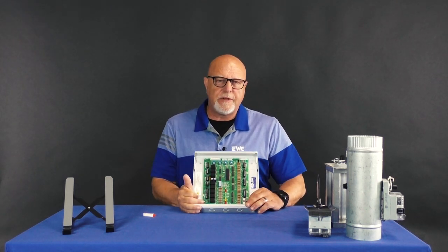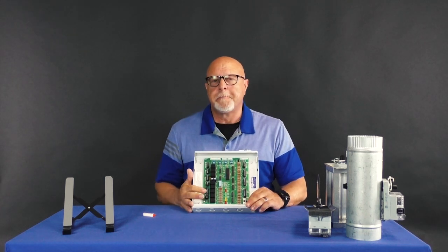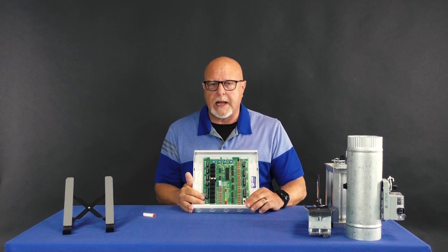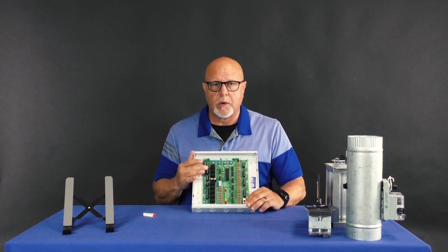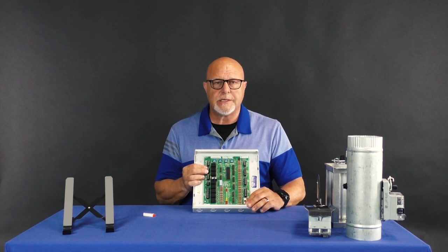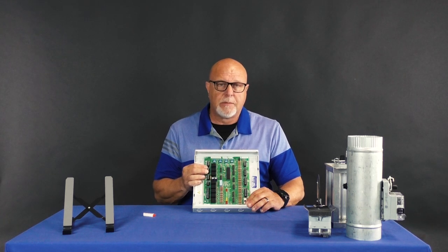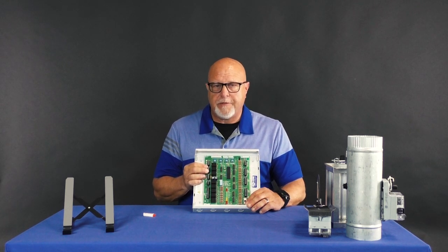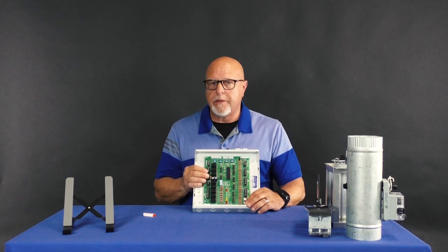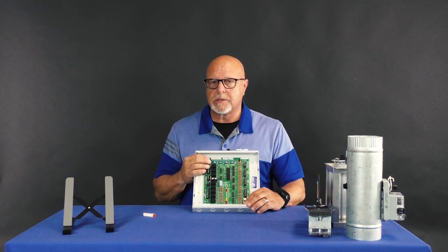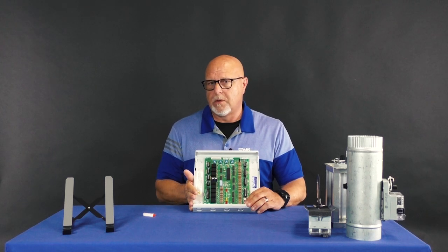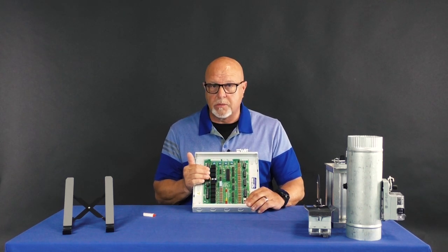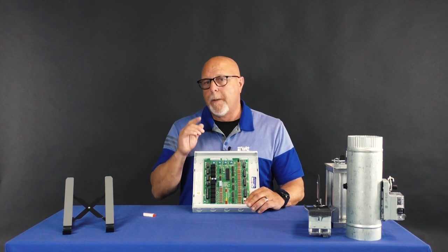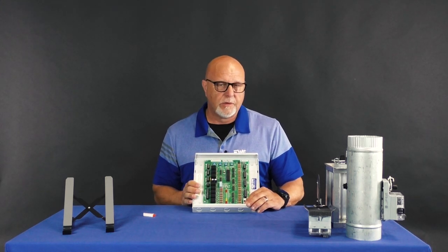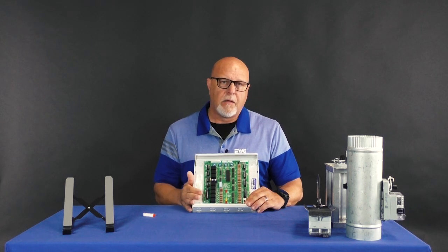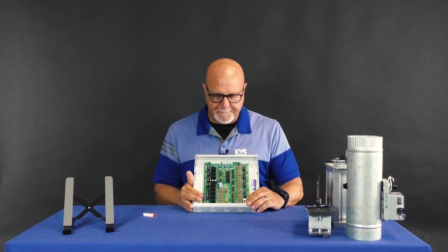So if you engage the 50% rule, meaning you turn it on, the board recognizes how many zones are on this board. On this board, for example, the BM Plus is 3 zones maximum capacity. The 50% rule states that more than 50% of the available zones must be calling for the same mode. So if you only have 2 zones connected to this 3-zone board, both of those zones would have to be calling for the same mode before I will allow that system to go to the higher stage.